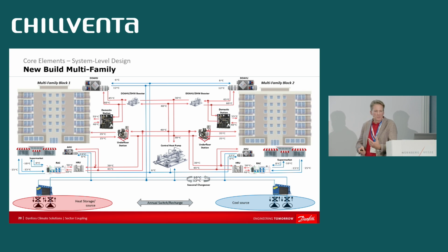So you only boost to what's required, and at the same time, with that same heat pump, you're also producing the cooling temperature to remove the latent energy in those same dedicated outdoor air handlers. Everything is hydronic—there's no DX here, so it's all integrated together.